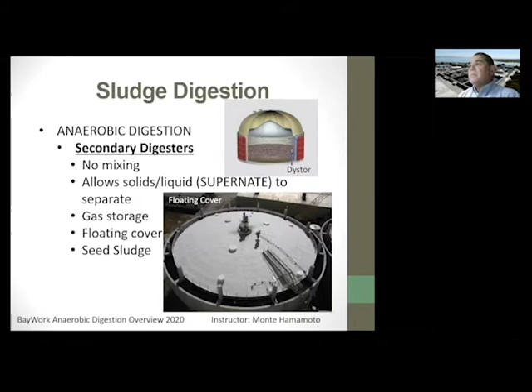Let's talk a little bit about the digester gas system itself. Digester gas, it's pretty valuable stuff. It has a heat value of 500 to 600 BTU, where natural gas has a heat value of 900 to 1200. It's not quite as efficient as natural gas because there are some impurities in digester gas and the methane concentration isn't quite as high, but it does have value. Biogas will burn at 55% methane, and biogas with at least 62% methane can be used as a fuel source.